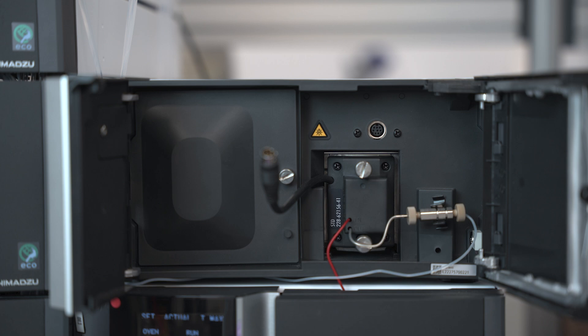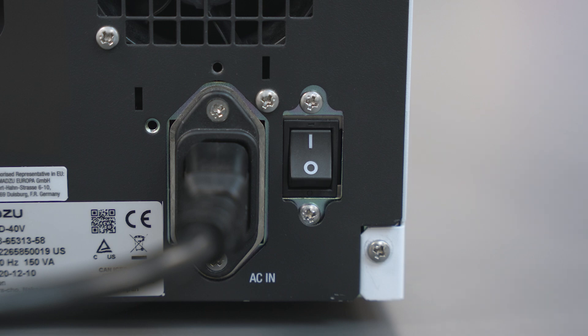First, we must remove the flow cell. To remove the flow cell, turn the instrument off from Lab Solutions. Once the instrument is shut down, turn the main power switch located by the power cable at the back of the detector off.